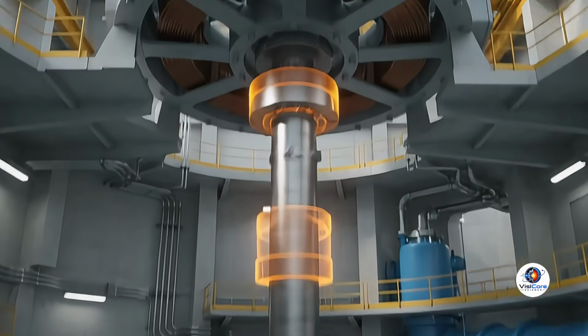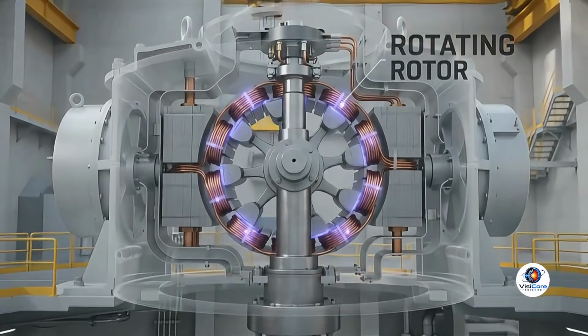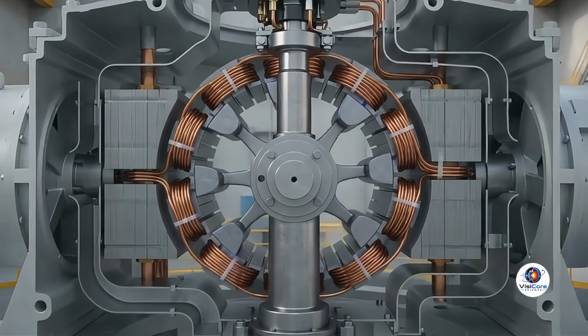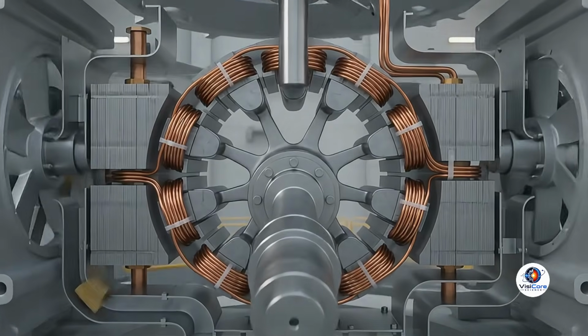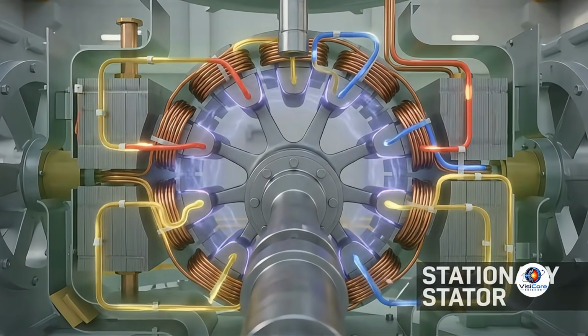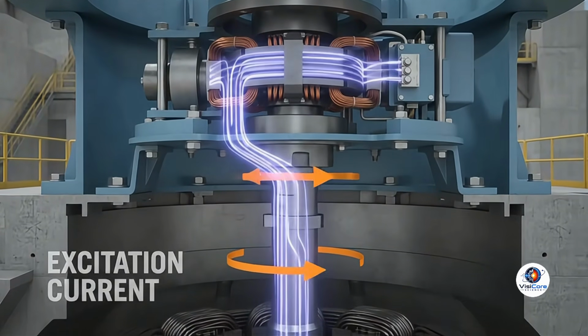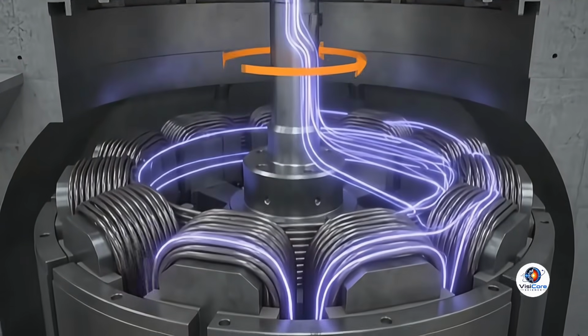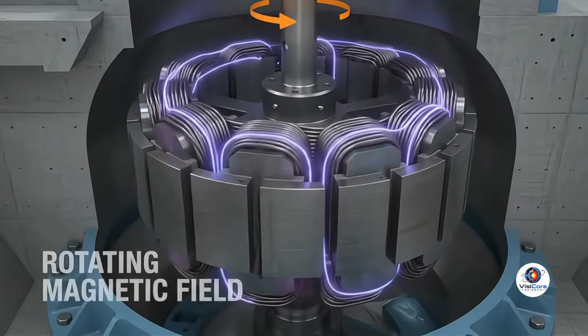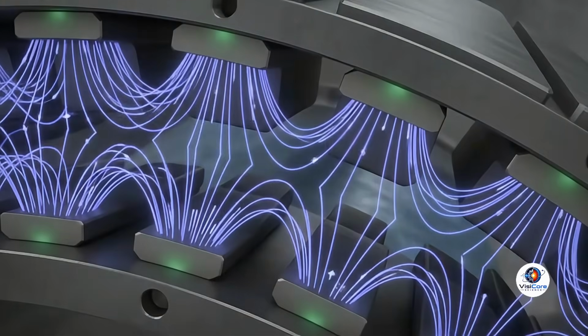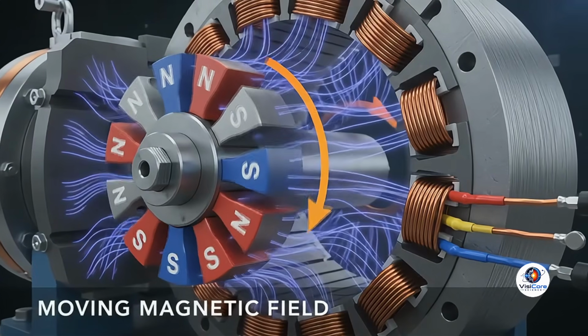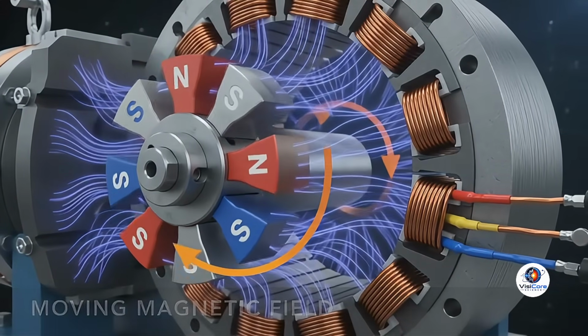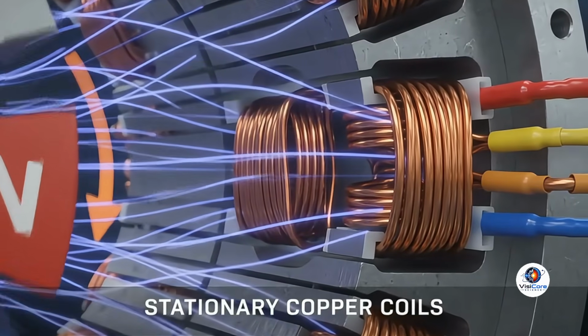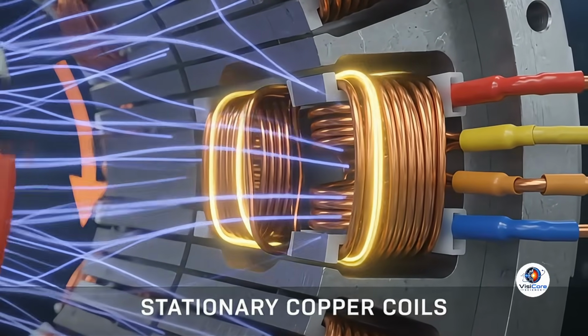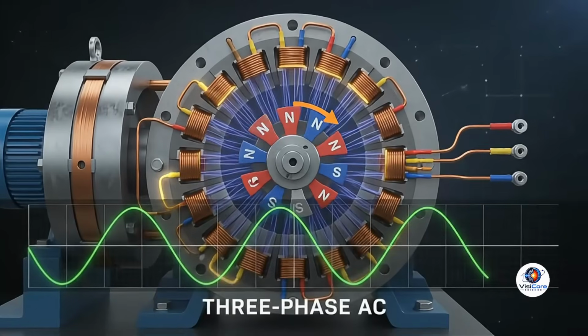Above the turbine is a synchronous generator. The shaft rotates its magnetic rotor inside a stationary ring of copper windings. The excitation system supplies controlled current to the rotor windings. This creates alternating magnetic poles that rotate with the shaft. As the rotating magnetic field passes the stationary copper windings, electromagnetic induction produces three-phase alternating electrical power.